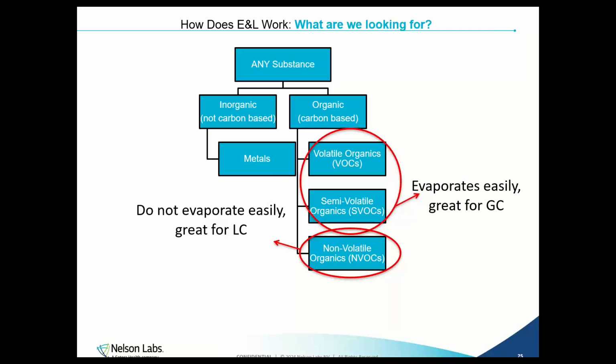Lastly, we can identify any non-volatile organic compounds with the LC-MS. All of the analytical sensitivity of this testing must be documented appropriately, as well as the relative response factors, internal standards used, and the correct analytical evaluation threshold derived from the applicable dose-based threshold. Now, there's quite a bit of finite detail that goes into these E&L studies, so please don't hesitate to reach out if help is needed to design one.